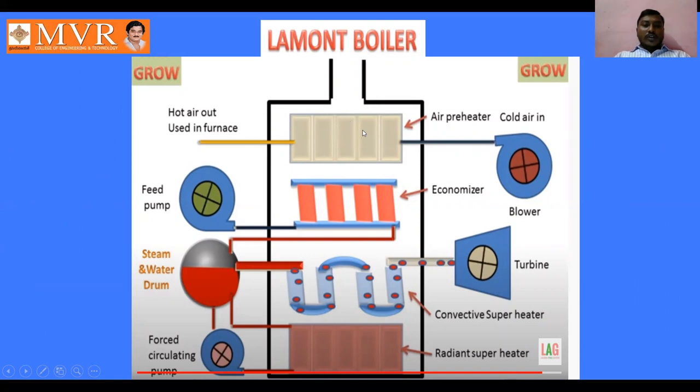and converted into hot air, and the hot air is used for the furnace purposes. And here we are going to feed the water by using this pump. We are going to feed water to the economizer where the water temperature is going to be raised. And it is going to enter the steam and water drum, where the steam as well as the water is going to be separated here.